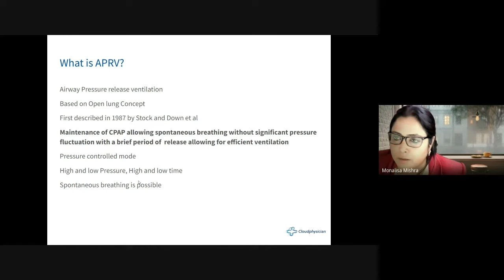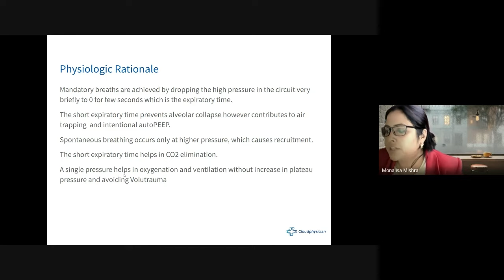Mandatory breaths are achieved by dropping the high pressure in the circuit briefly to 0 for a few seconds, which is the expiratory time. The short expiratory time will prevent alveolar collapse, however, it contributes to air trapping and intentional auto PEEP. Spontaneous breathing occurs only at higher pressure, which causes recruitment. The short expiratory time will help in CO2 elimination. A single pressure helps in oxygenation and ventilation without increasing the plateau pressure and avoiding volutrauma.